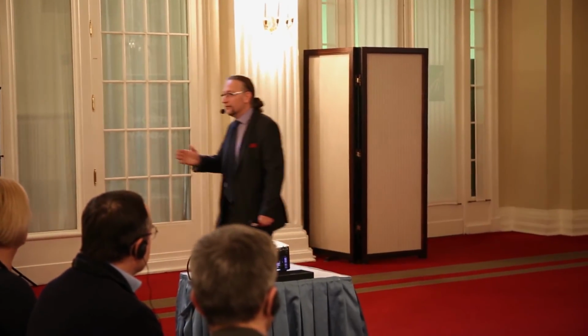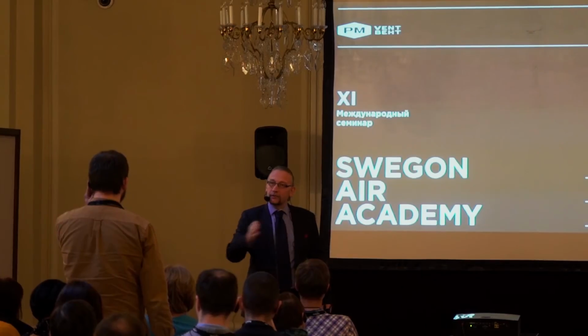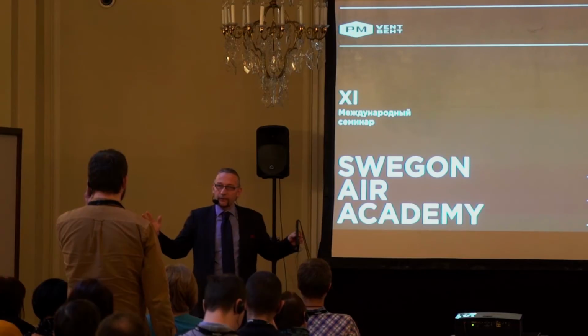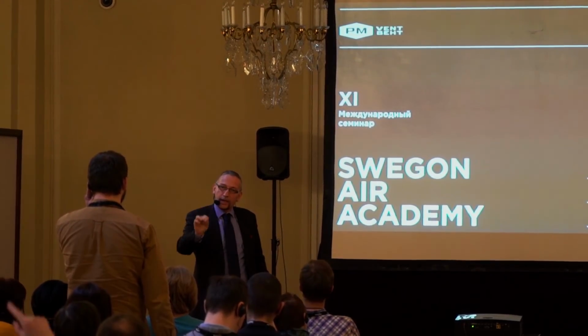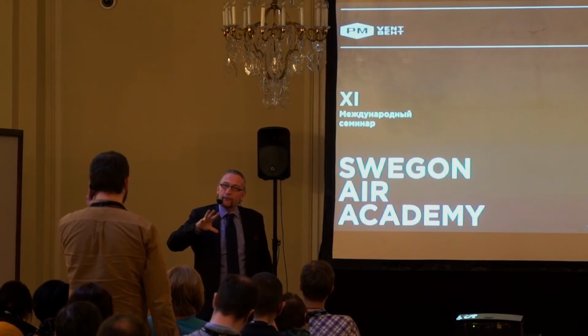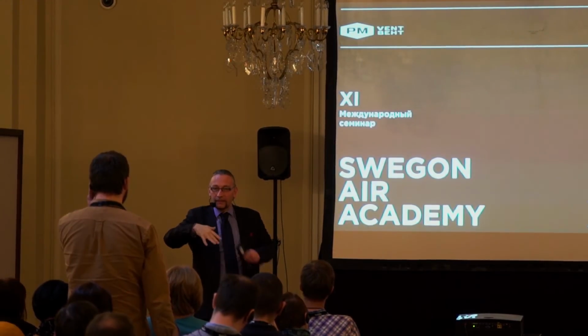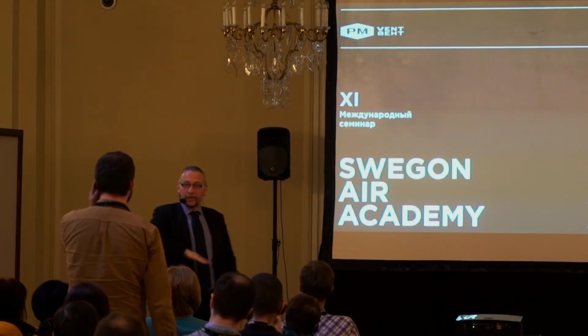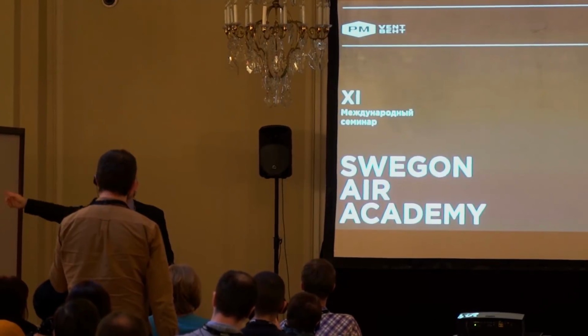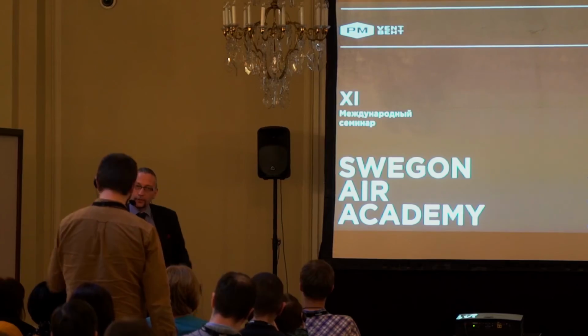This could be 200 Pascal, 190, 180, 250, 160, depending on what it needs right now. Because the dampers should be as open as possible, and the pressure impulse that goes to the air handling unit goes up and down. And by that, the air volume in the building goes up and down. But the dampers should always be as open as possible. So if this room is 50%, and that room is 20%, then this room should be 100%, and that room should be 40%. So yes, you still have some pressure over there, but much less than before. So you reduce the pressure as much as possible. And by that, the fan power goes down.